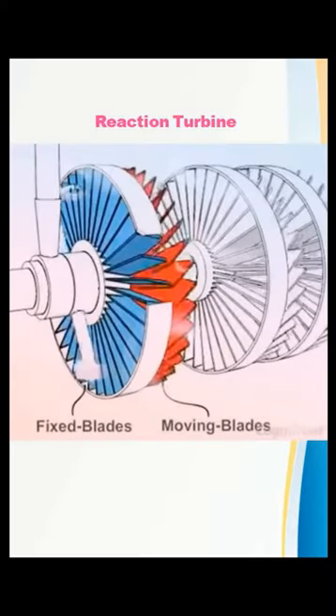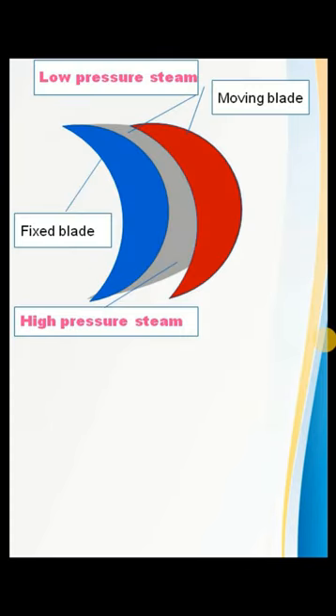In a reaction turbine, high pressure steam coming from the boiler is passed directly through the fixed and moving blades instead of a nozzle. The blades are designed such that the steam flowing between the fixed and moving blades is subjected to a nozzle effect.